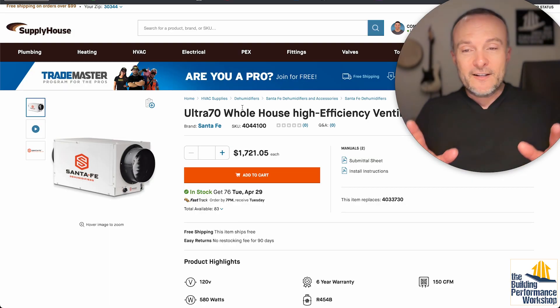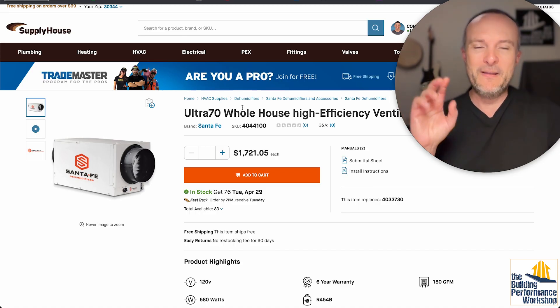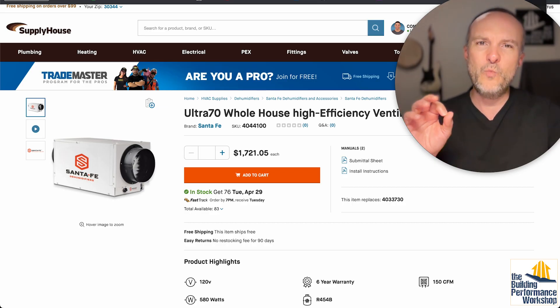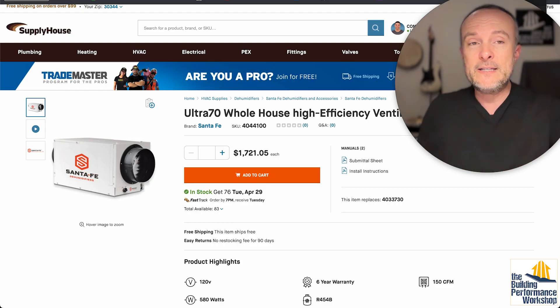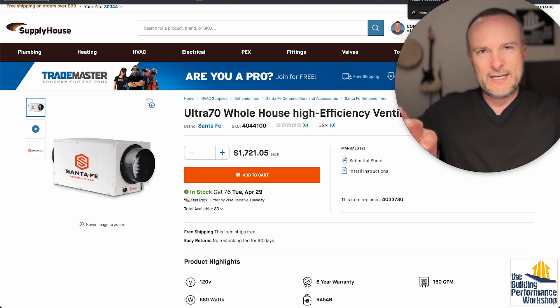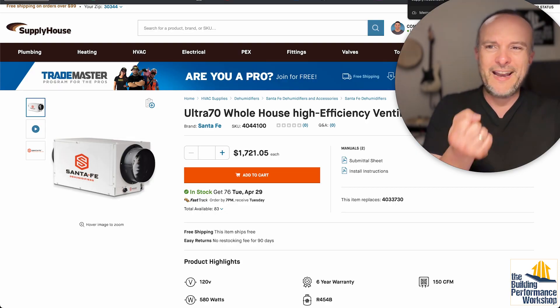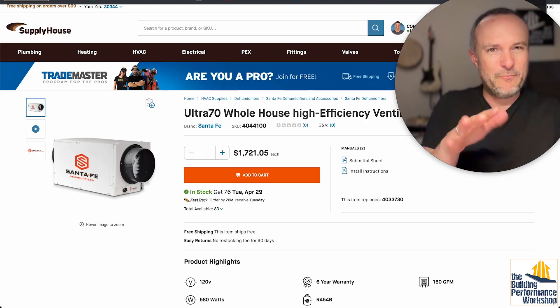One final caveat: the basement scenario I mentioned earlier where air hits 72% relative humidity — if you ever have basement dehumidifiers not working well, it may be because it's 65 degrees down there. These dehumidifiers don't run well at colder temperatures; they max out on efficiency around 70 degrees. At lower temperatures they can only pull humidity down to about 40% relative humidity before they start returning moisture to the air — so that's roughly the break-even point.